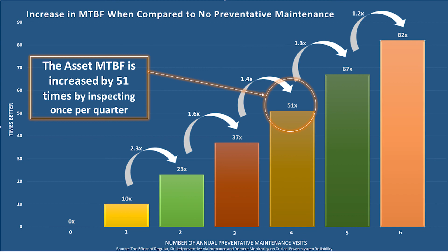So there's a couple of things that we talk about. There was a study done by the guys from Emerson where they looked at the effect of increasing the frequency at which they do condition-based inspection on electrical and mechanical assets. Basically they found that if they went from not doing any condition-based inspections to doing once a year, there was a 10 times increase in mean time between failure. That's huge, that's massive, 10x. But if they went from annual to twice a year inspections, there was still another 2.3x increase. If they went to quarterly inspections from annual, it was a 5.1x increase. This inherently just makes sense - the more often we inspect things, the more likely we are to catch the problems early in the PF curve and then able to take smarter decisions about corrective action.